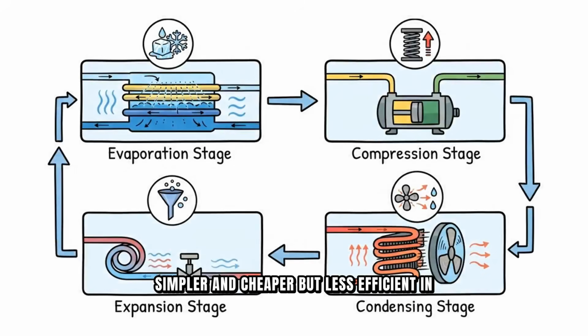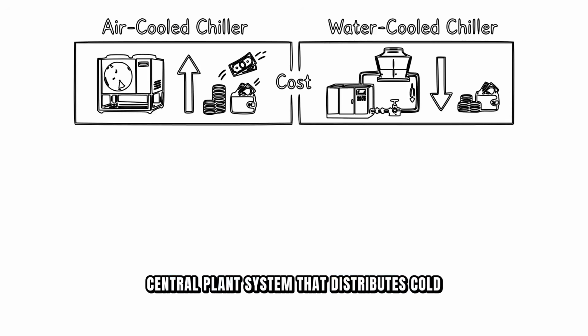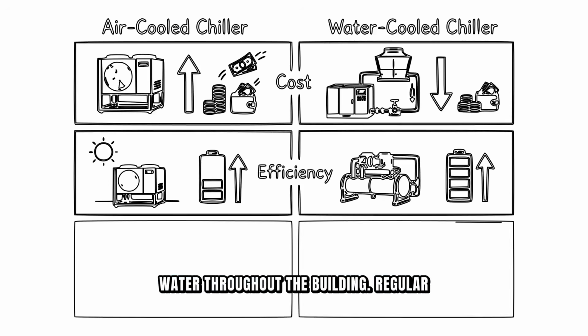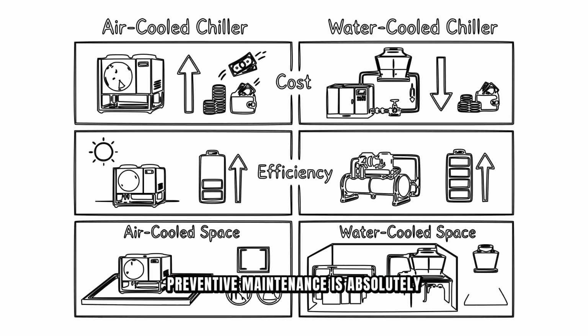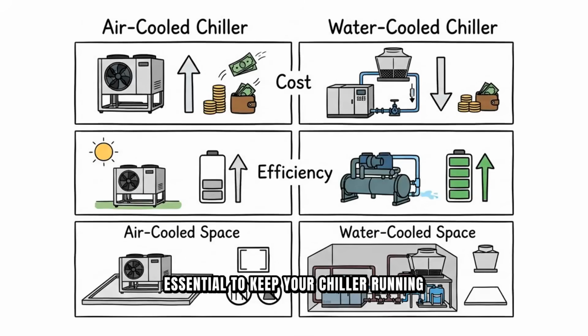Air-cooled chillers are simpler and cheaper but less efficient in hot weather, while water-cooled chillers are more efficient but more complex and expensive. Chillers work as part of an integrated central plant system that distributes cold water throughout the building. Regular preventive maintenance is absolutely essential to keep your chiller running efficiently and to prevent costly breakdowns.